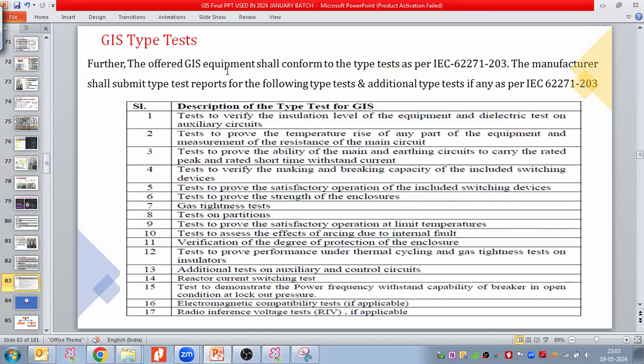Further, the offered GIS equipment shall conform to the type test as per IEC 62271-203. The manufacturer shall submit type test reports for the following type tests and additional type tests, if any, as per 62271-203, or any additional type tests that the manufacturer or client asks for in their technical specifications.